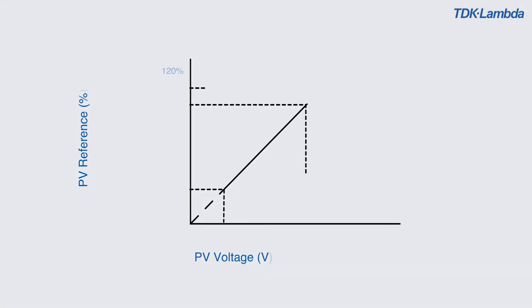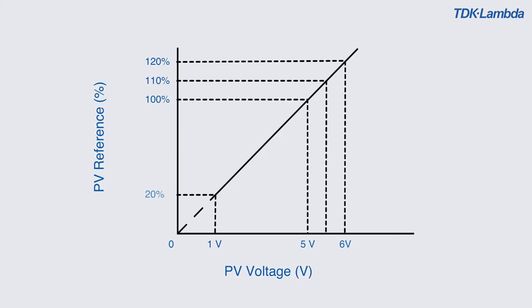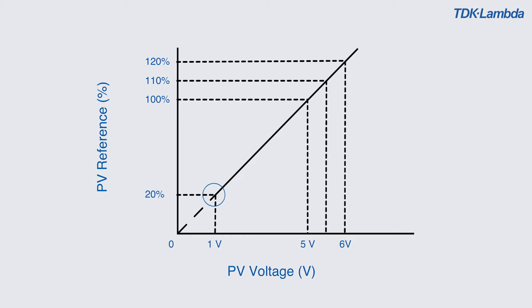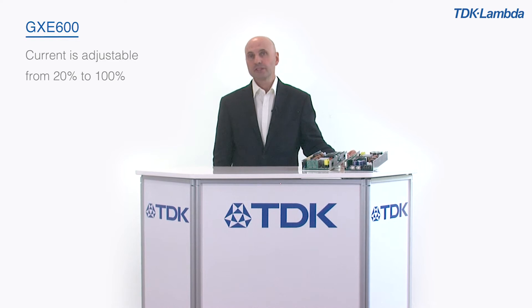The diagram shows the external programming voltage, PV, adjusting the output voltage from 20% to 120% of the nominal 24 or 48V output. Current is adjustable from 20% up to 100%.